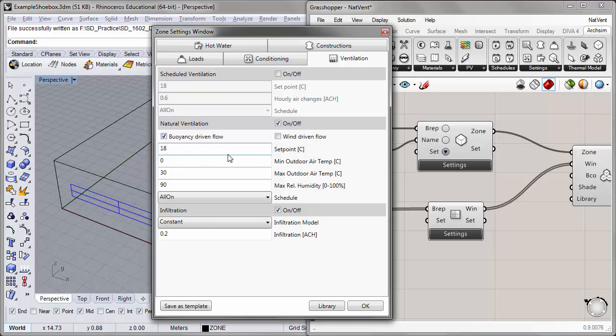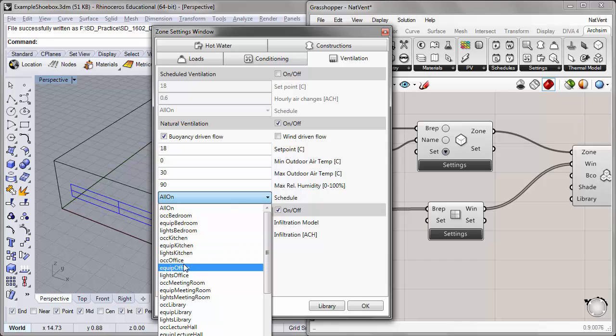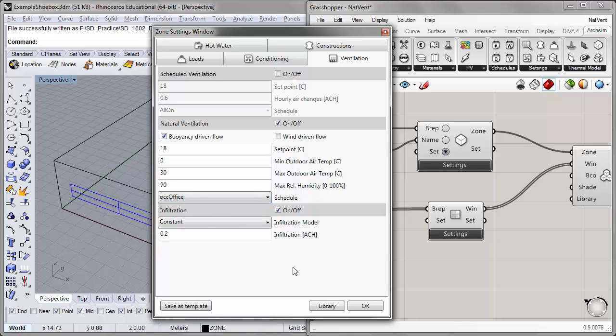This set point is the temperature to which the natural ventilation should cool to. We can indicate a lower outdoor air temperature limit for using natural ventilation and leave the default for now. We can also indicate a maximum outdoor air temperature — above which we don't want to use natural ventilation — and I'll leave that at 30 degrees Celsius. We can also provide a schedule for natural ventilation. For this tutorial, let's use natural ventilation whenever people are in the office, so we'll use the occupancy schedule to drive it. I'll press OK.